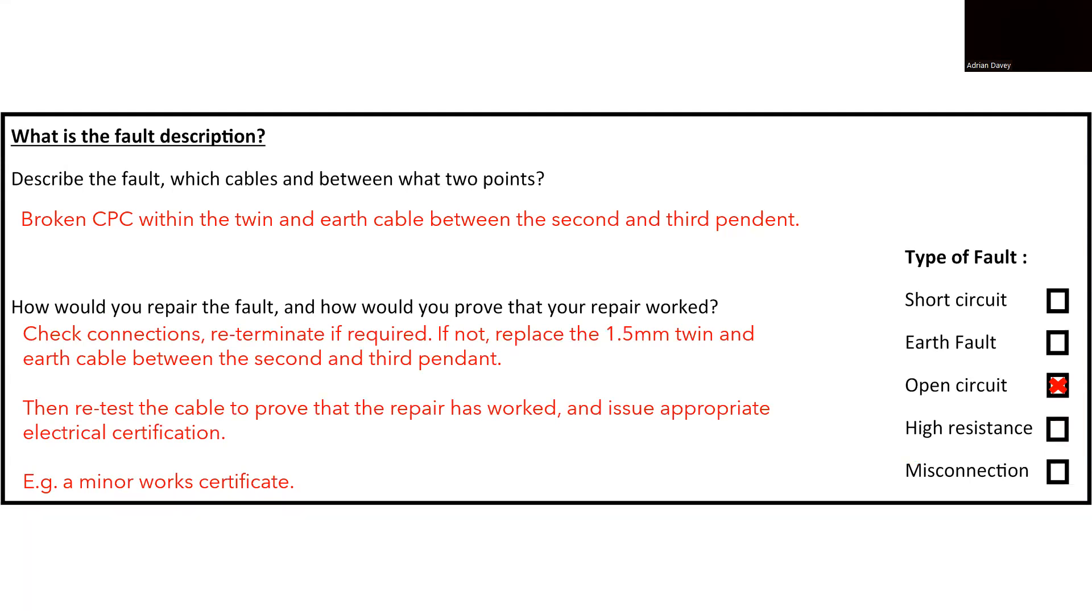In practice, it is essential to conduct thorough checks on connections and re-terminating if required, before concluding that a partial rewire is required. If it is confirmed that the cable was indeed the source of the fault, a cost analysis should be performed to compare the expense of cable replacement with the cost of locating and repairing the break within the building structure. The decision should be based on the available evidence. Once the necessary repairs have been made, it is crucial to conduct retesting to verify the success of the repairs and to ensure that the electrical system is now in compliance with safety standards. Depending on the nature of the repair, it may also be necessary to issue a minor work certificate.